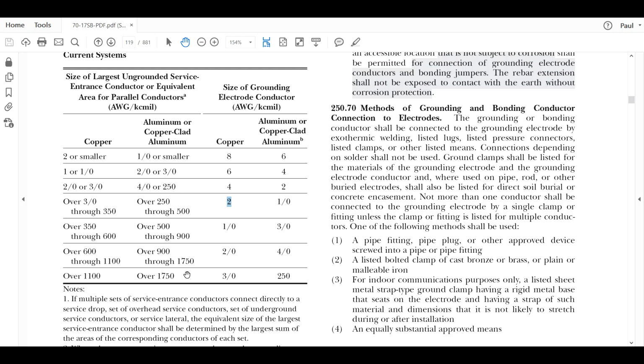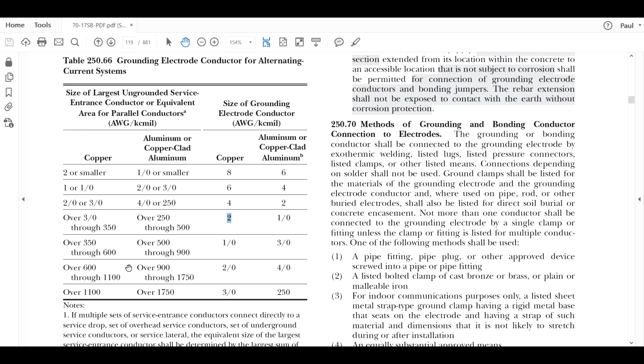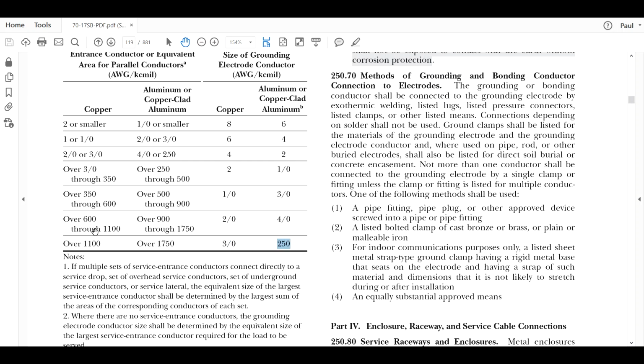The only difference really in the two tables is that once you get sizes of over 1100 kcmil copper or 1750 aluminum, when it comes to grounding conductors, bonding conductors, system bonding jumpers or supply side bonding jumpers, then you would have to use a 12.5% rule, and it can't be larger than that if your conductors happen to be larger than that, or even if parallel equivalents were larger than that. Then you run into that aspect. But when it comes to the grounding electrode conductors, at no time do they have to be any larger than a 3/0. That's the maximum size, and it would be 250 for aluminum. It's the maximum size that your grounding electrode conductor would have to be. Never has to be larger than that.